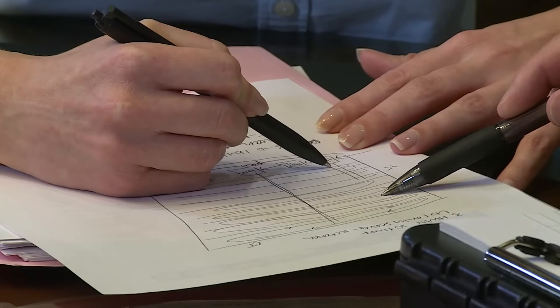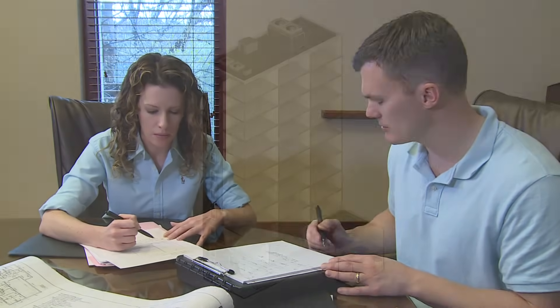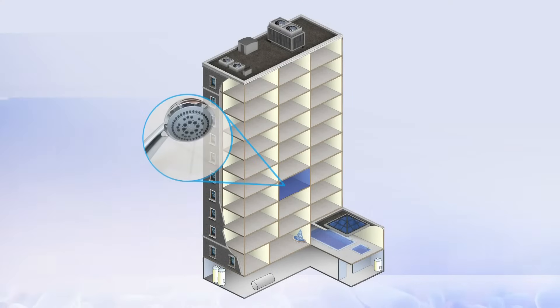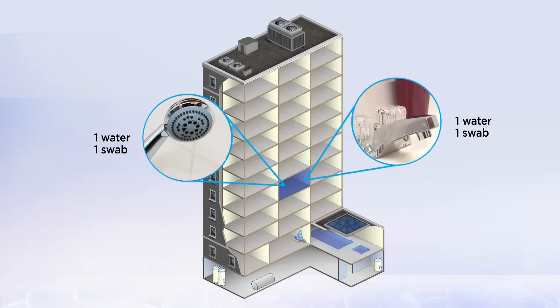In this example, let's tally the number of samples we'll need. You should collect two types of samples from each outlet or device, a one liter bulk hot water sample, and a swab of the biofilm.